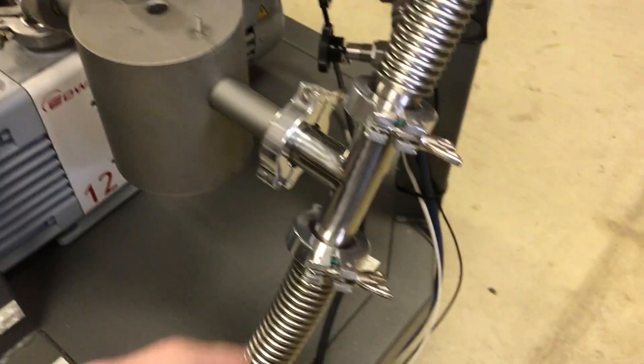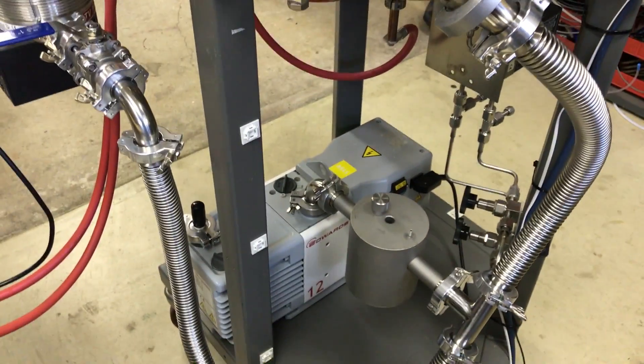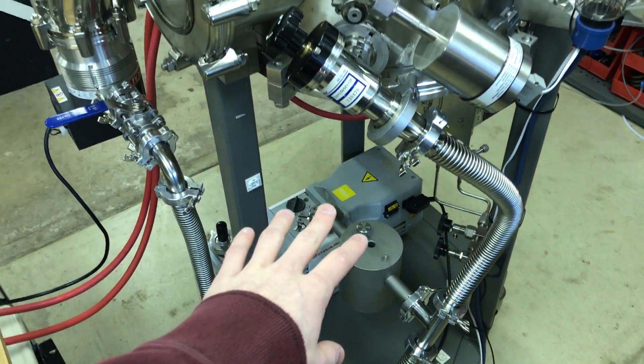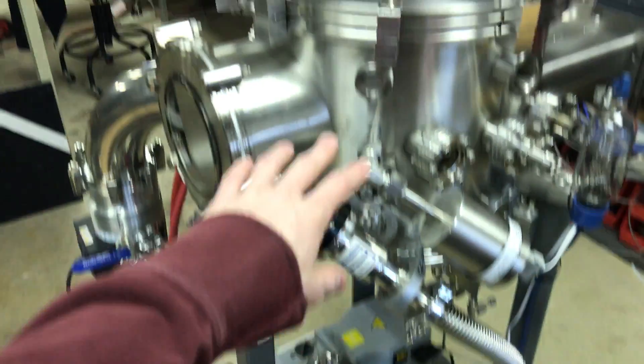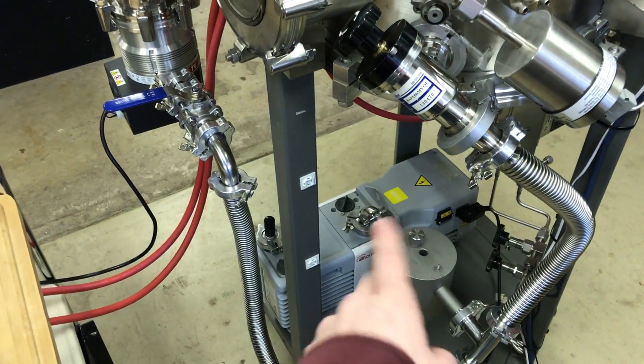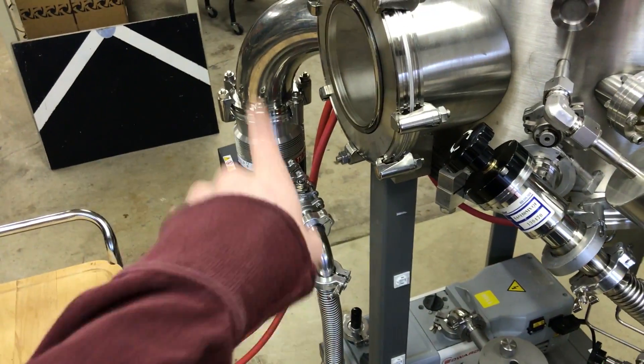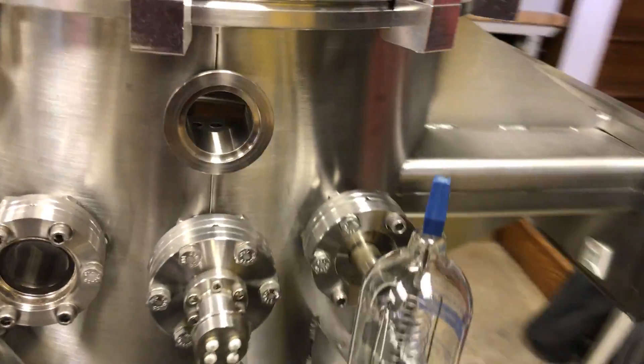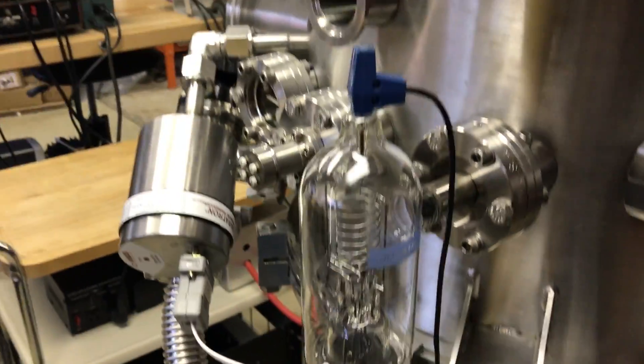I'm going to be using one of those to measure the backing pressure. I might tack it onto this T here or something, and that will allow me to measure my low vacuum side independently from the high vacuum, and just make sure that the mechanical pump is doing its job while we're backing the turbo.